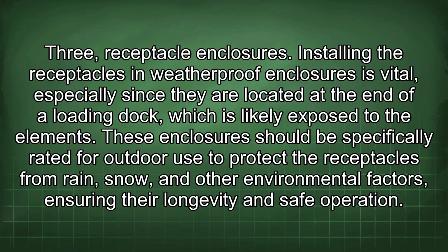3. Receptacle enclosures. Installing the receptacles in weatherproof enclosures is vital, especially since they are located at the end of a loading dock, which is likely exposed to the elements. These enclosures should be specifically rated for outdoor use to protect the receptacles from rain, snow, and other environmental factors, ensuring their longevity and safe operation.